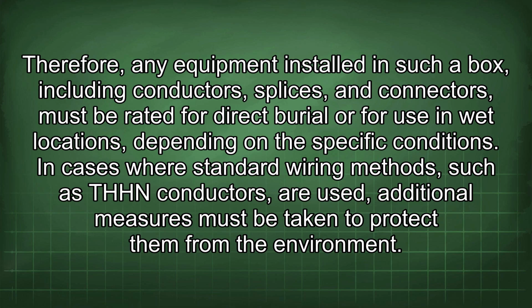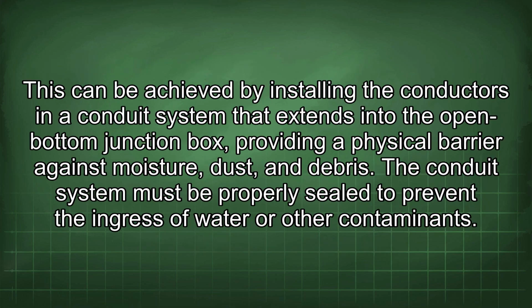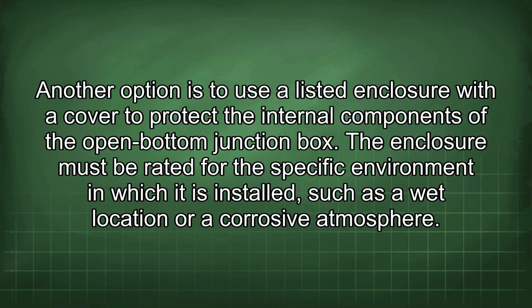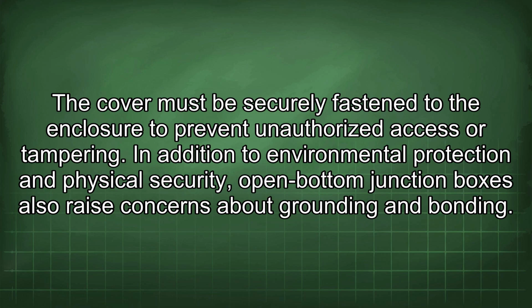In cases where standard wiring methods, such as THHN conductors, are used, additional measures must be taken to protect them from the environment. This can be achieved by installing the conductors in a conduit system that extends into the open bottom junction box, providing a physical barrier against moisture, dust, and debris. The conduit system must be properly sealed to prevent the ingress of water or other contaminants. Another option is to use a listed enclosure with a cover to protect the internal components of the open bottom junction box. The enclosure must be rated for the specific environment in which it is installed, such as a wet location or a corrosive atmosphere. The cover must be securely fastened to the enclosure to prevent unauthorized access or tampering.